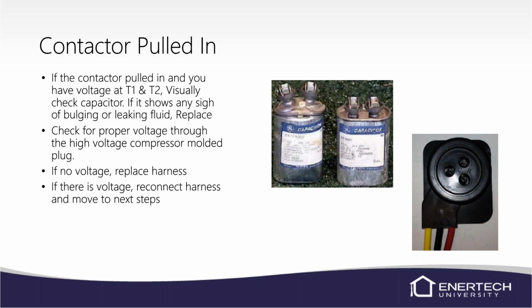We don't have a huge issue with capacitors, but they are what they are. They bulge and break and drip oil all over the place sometimes, and they're nice and stinky. So definitely check capacitors, and check for proper voltage to the capacitor and also check the microfarads of the capacitor. It usually needs to be within 5%. Sometimes it's 10%, depending on the brand, but make sure you've got the proper capacitor and that it's functional.